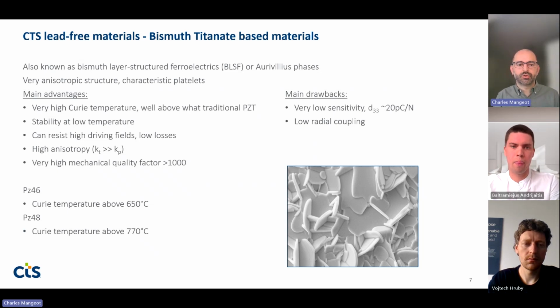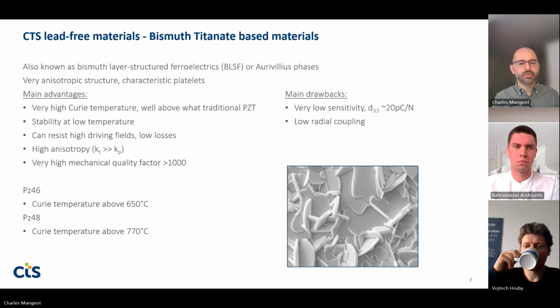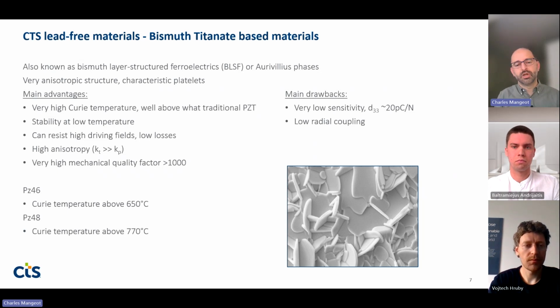And also because of the structure, we have high anisotropy. So the thickness coupling is much superior to the planar coupling, which is an advantage when you're developing a thickness mode transducer. In addition, we have a material that has a very high quality factor, mechanical quality factor, which means it can be used for resonant applications. The drawback of these materials is that the coupling, or more precisely the sensitivity, so the piezo coefficients are relatively low. So this needs to be taken into account. We have two materials in that range, PZ46, PZ48, with different Curie temperatures.